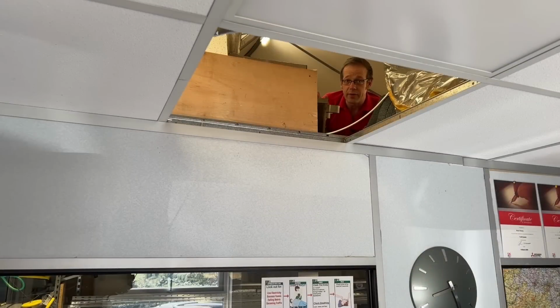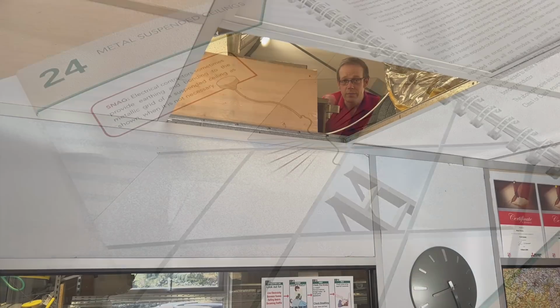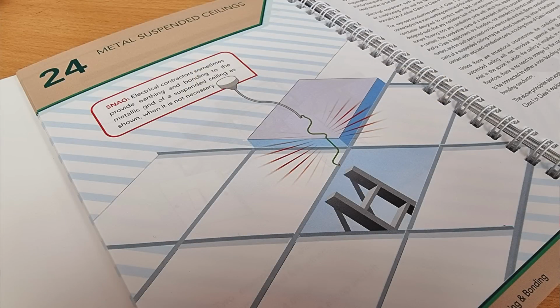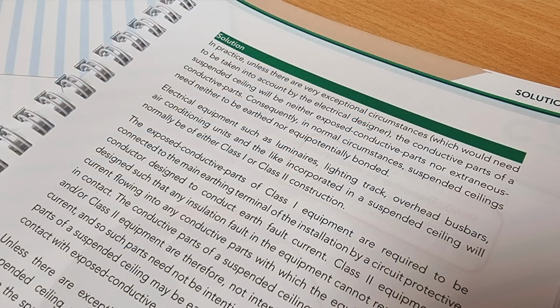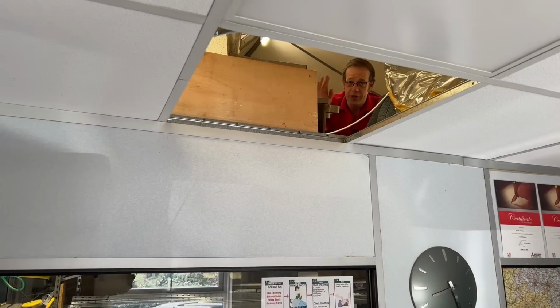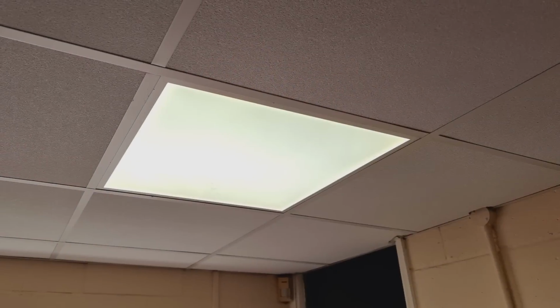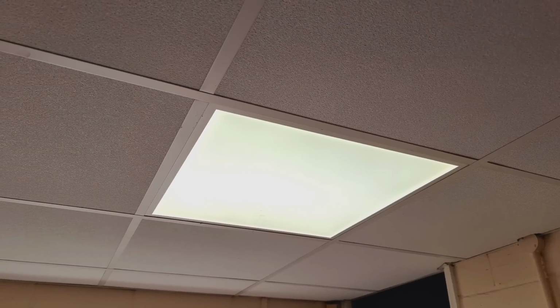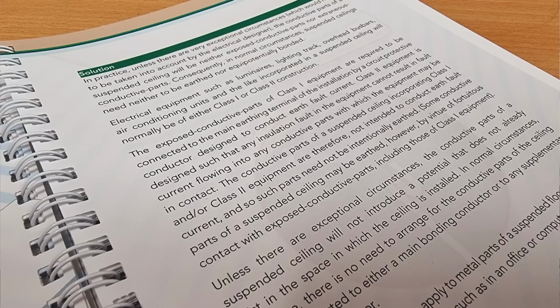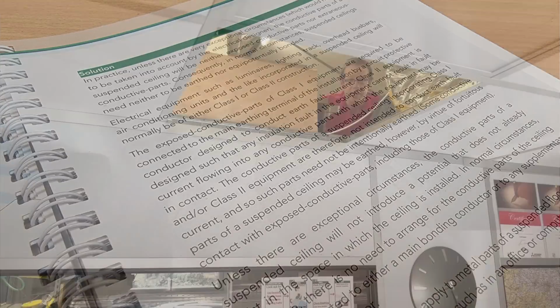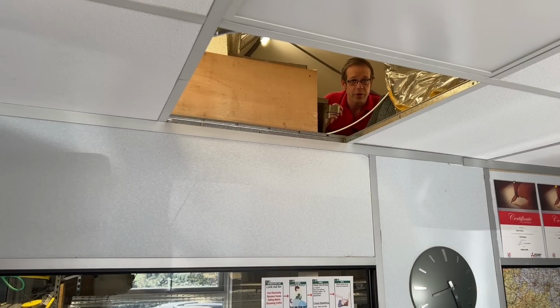So coming back to our ceiling grids, we've covered the fact that we shouldn't be using them to support cables. But we may be thinking, well, what happens if a fault occurs in a fitting that's sitting in the ceiling grid? Won't that then cause the grid to become live? Well, Volume 1 of Snags and Solutions by the NICEIC comments on this, making the point that any electrical equipment installed in a suspended ceiling would normally either be Class 1 or Class 2. If it's Class 2, then even if the outer shell is made of metal and rests on the ceiling grid, this class of equipment should be made in such a way that a fault occurring inside it can't result in fault current flowing into any conductive parts with which the equipment may be in contact. So in other words, a fault in the equipment won't lead to the metal grid it's touching becoming live.